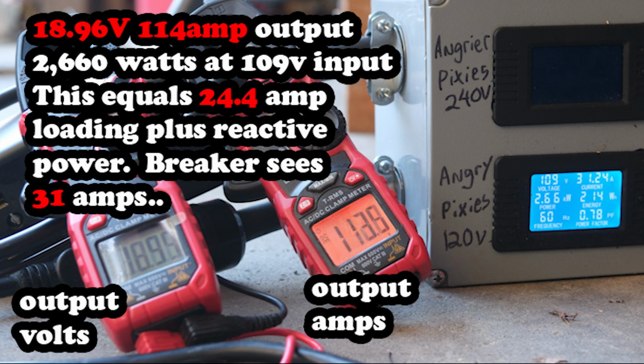drops so low. And universally, you're going to find this is the problem with every 120 volt capable welder. All of them overload breakers, and all of them are going to be almost impossible to run on a generator, with the exception of some older school transformer machine will likely weld at reduced output. But again, it's still going to trip the breaker when you try and weld anything decent. That's why you really need to stick to 240 volts off a generator and a 240 volt welder to get any kind of reasonable output.